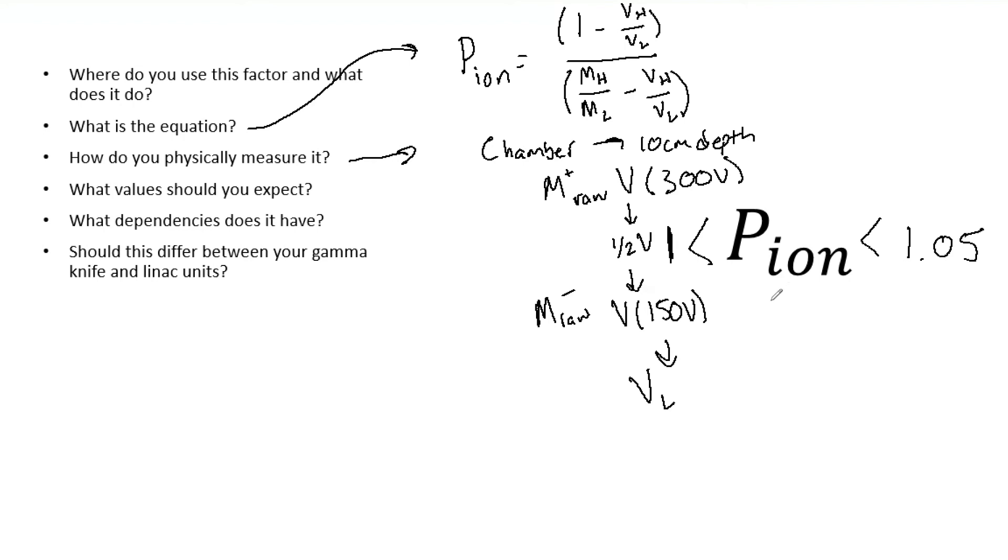Another thing though, your P ion also has to be greater than 1. Because think about it, you are essentially correcting for ions that are recombining, and you can't recombine and get more charge. It doesn't make any sense. So the value has to be greater than 1 but it must be less than 1.05.